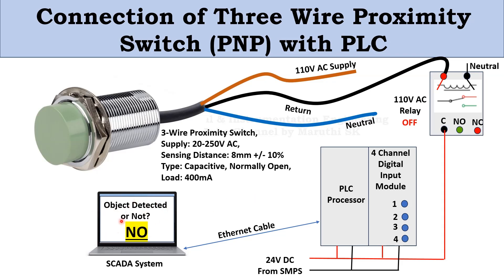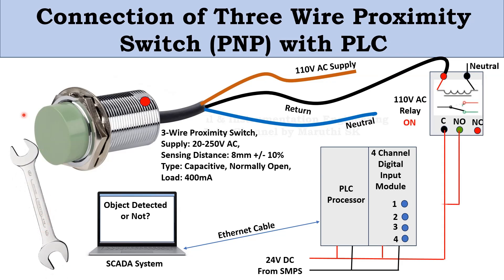Currently, no object is detected nearby the proximity switch, so the SCADA screen and PLC indicate 'Object Detected: No.' Now we bring the object near the proximity switch — the proximity switch detects the object and gives the indication lamp. 110V AC is applied to the proximity switch and returned through the black wire to the 110V AC relay coil. The relay turns on, NO contact changes to closed, and 24V DC passes through NO contact to channel number 1 of the digital input module. The PLC processor sends signal to the SCADA — Object Detected: Yes.